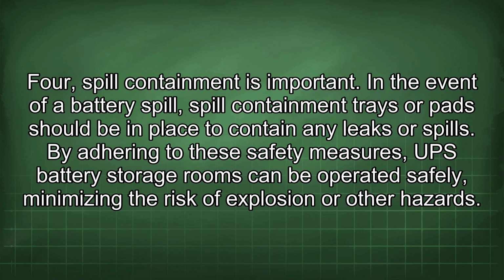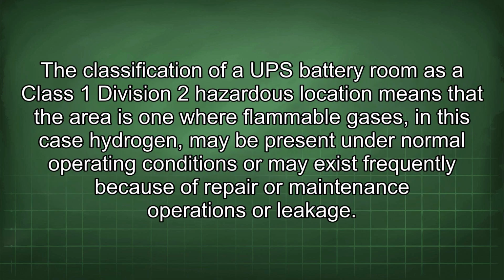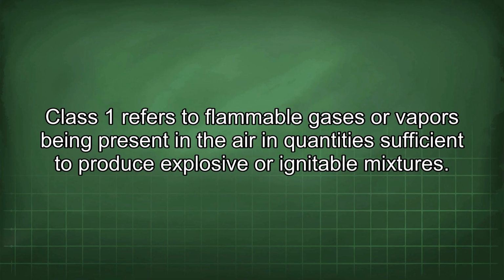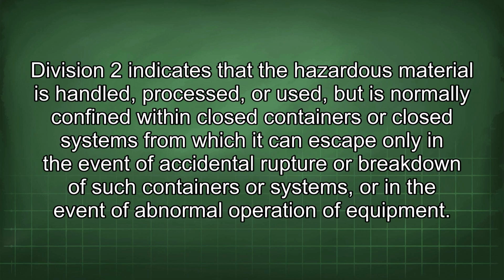explosion or other hazards. The classification of a UPS battery room as a Class 1 Division 2 hazardous location means that the area is one where flammable gases, in this case hydrogen, may be present under normal operating conditions or may exist frequently because of repair or maintenance operations or leakage. Class 1 refers to flammable gases or vapors being present in the air in quantities sufficient to produce explosive or ignitable mixtures. Division 2 indicates that the hazardous material is handled, processed, or used, but is normally confined within closed containers or closed systems from which it can escape only in the event of accidental rupture or breakdown of such containers or systems, or in the event of abnormal operation of equipment.